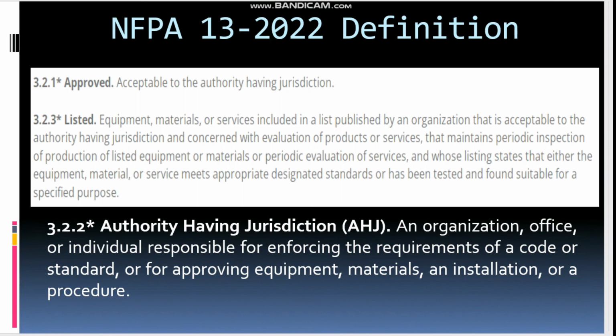So as per NFPA, approved means acceptable to the authority having jurisdiction. Only the AHJ has the authority to approve any material. Listed is different. Listed means an organization, a third party, that is acceptable to the AHJ. That may be any organization: FM, UL, VDS, LPCB, different organizations or third parties that are acceptable to the AHJ. What they will do is get multiple samples from the manufacturer and do different types of inspection or tests, and finally, based on their requirements, they will say that this product is okay and it is listed. This is the difference between approved and listed.